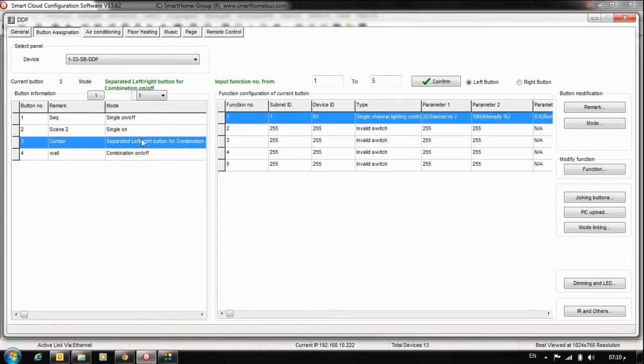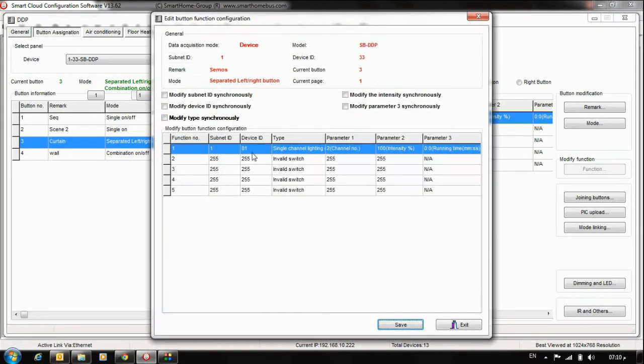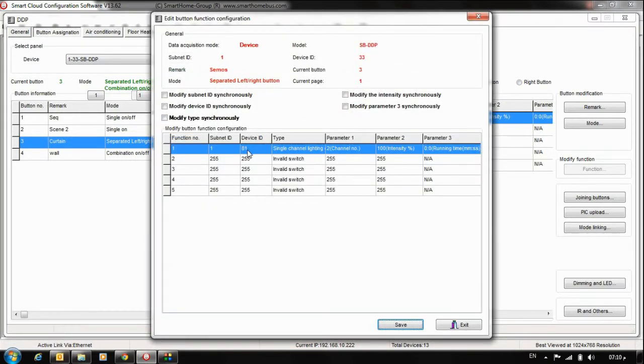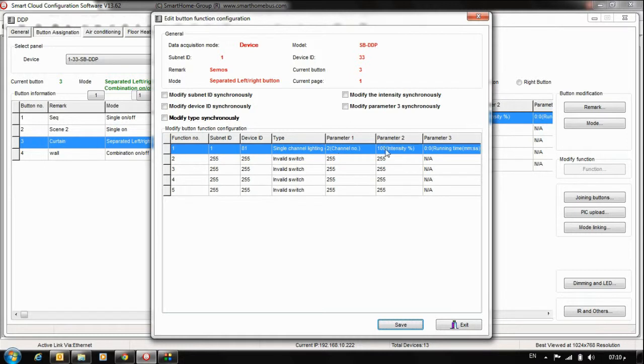Once I choose Separated, I have Left and Right. And Left, I'll choose my relay, the device ID for my relay which is already 81. The type, Single Channel, Parameter 1 I need, that means channel 2. And Parameter 2 I need it 100%, full, because this one is relay.